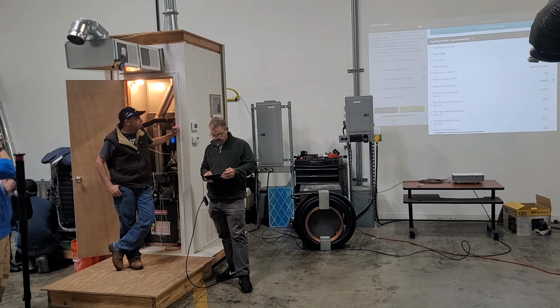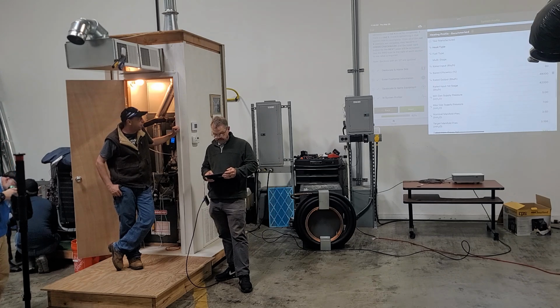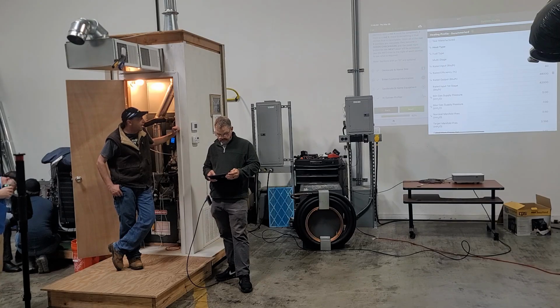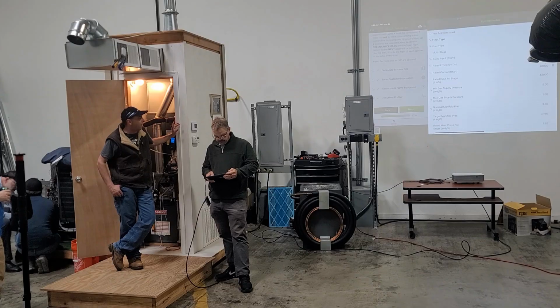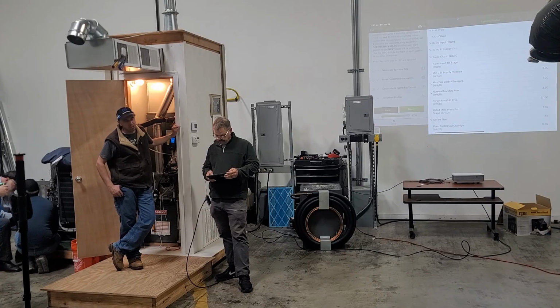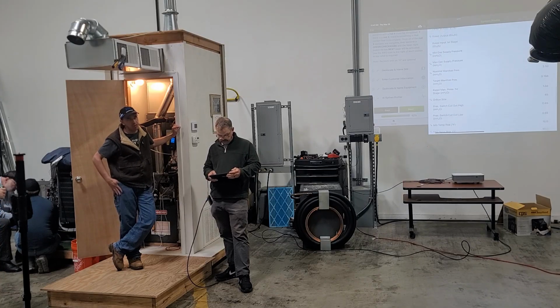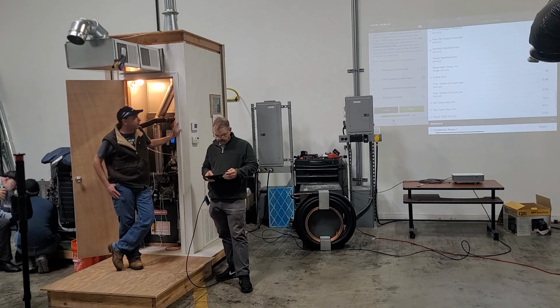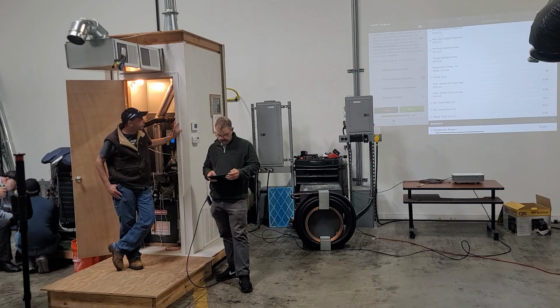Now we're into the furnace profile, this is the important part. Again, verify that the AI read the label correctly. Everything on this page is on the label for this furnace, with the exception of the pressure switch. There's no pressure switch info on the label, I had to get that off of the switch itself. So that's everything.